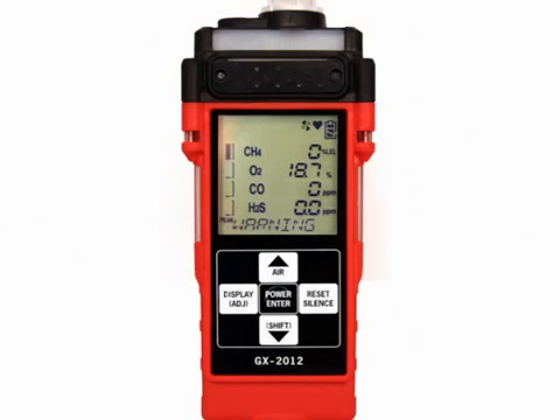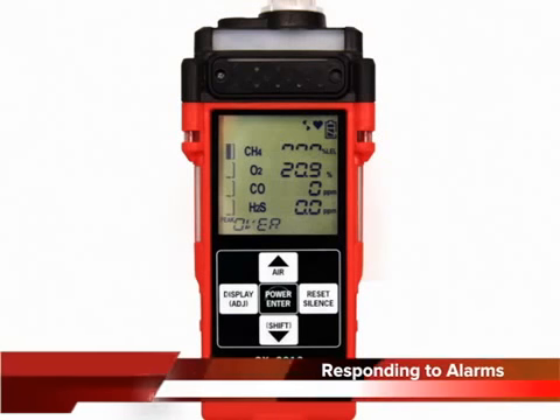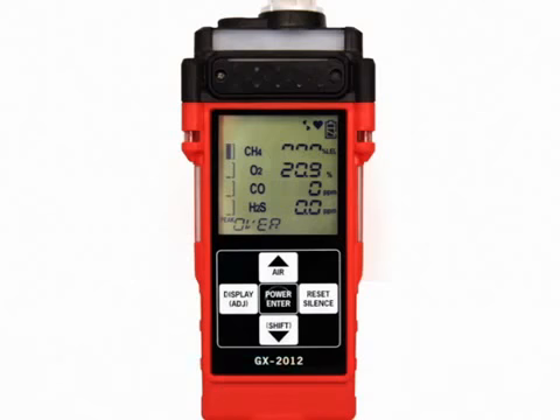With alarm silence set to off in maintenance mode, you cannot silence the buzzer while the gas reading is beyond the low alarm setting. An overrange condition may indicate an extreme combustible gas, toxic gas, or oxygen content condition. Take immediate action and confirm the gas levels in the area with a different GX2012 or with another gas detecting device. Determine which gas alarm has been activated. Follow your established procedure for an increasing gas condition.